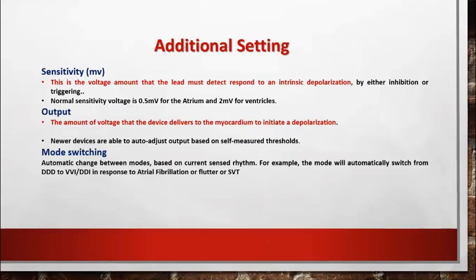Output is the amount of voltage that the device delivers to the myocardium to initiate depolarization. Now, newer devices are able to auto-adjust output based on self-measured thresholds. And there are new pacemakers which automatically change between modes based on the current sensed rhythm. For example, the mode will automatically switch from DDD to VVI or DDI in response to atrial fibrillation, flutter, or SVT.